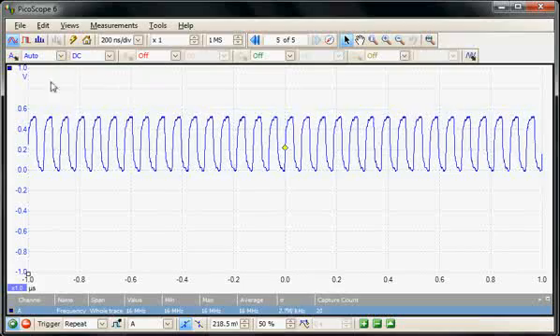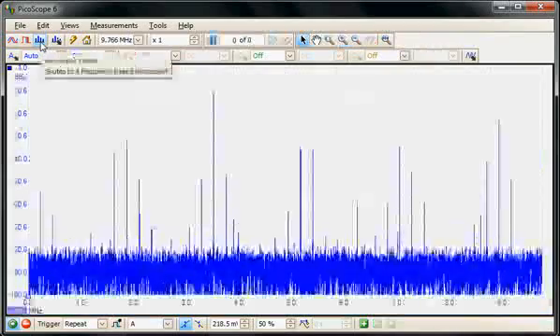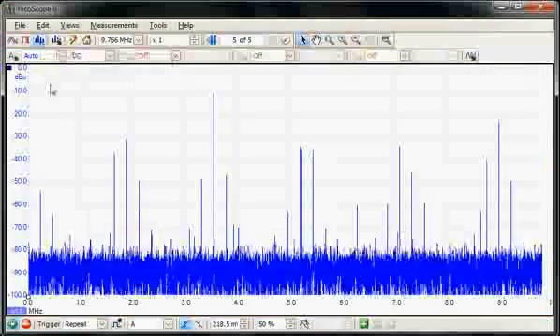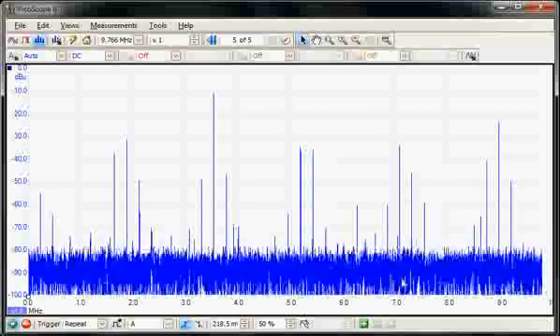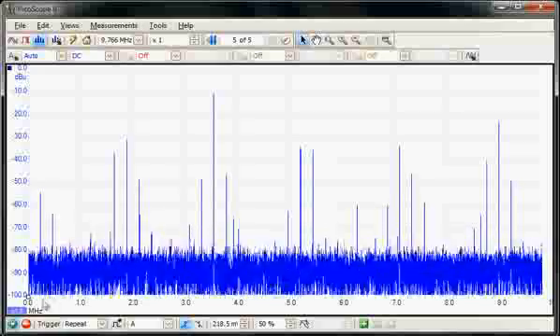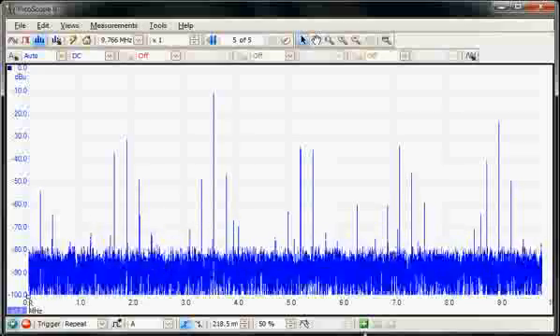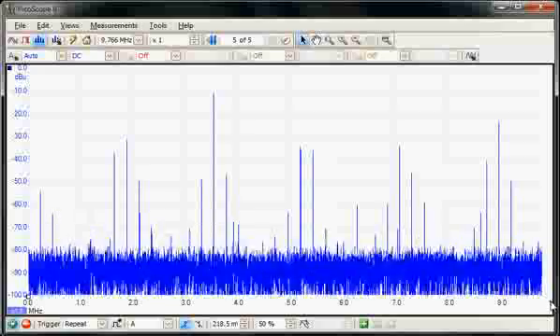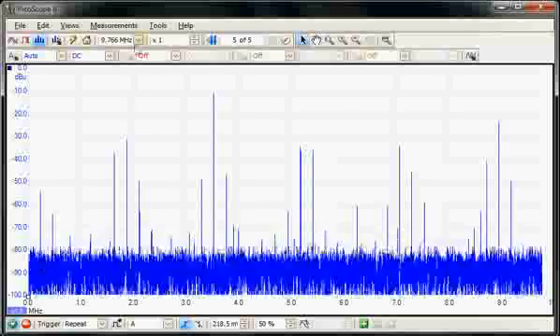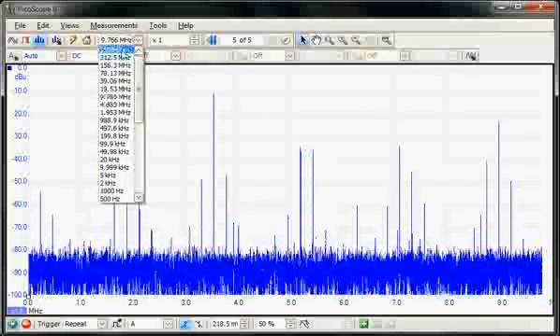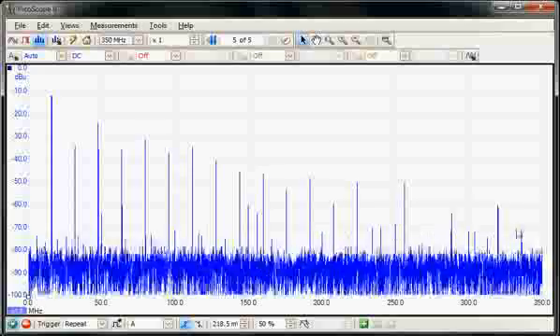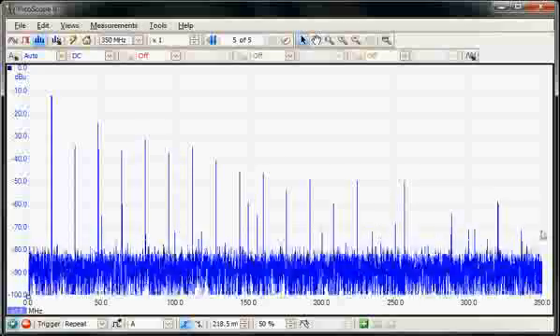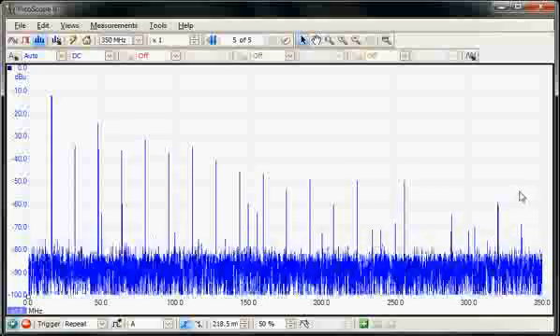So I'll change the acquisition to spectrum, and now we're in a spectrum display where we're displaying amplitude against frequency. In this particular display, we're going from DC up to 10 MHz. It is possible to increase the bandwidth up to 350 MHz, so now we're displaying up to 350 MHz, which is the full analog bandwidth of the instrument.